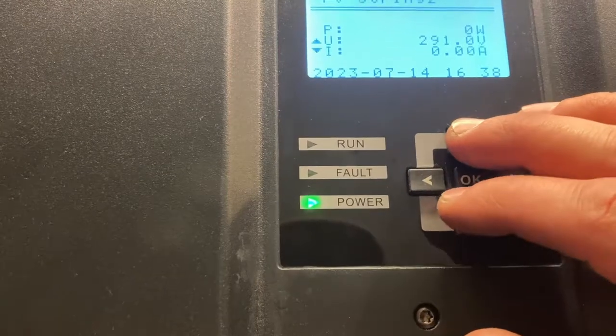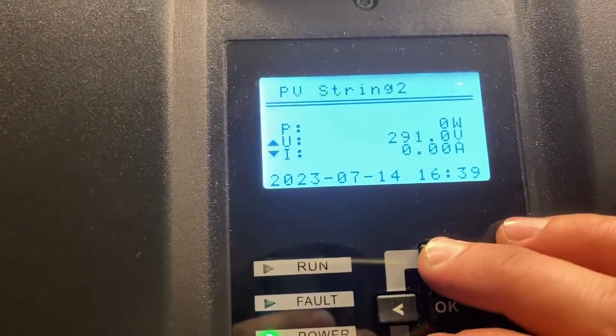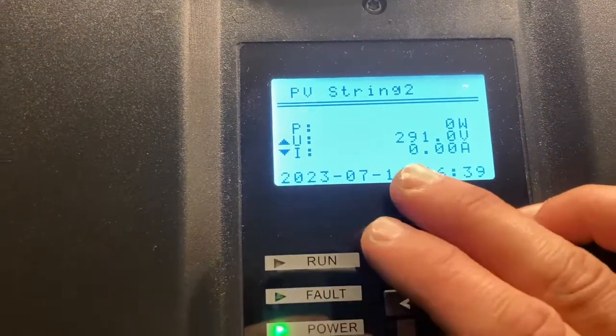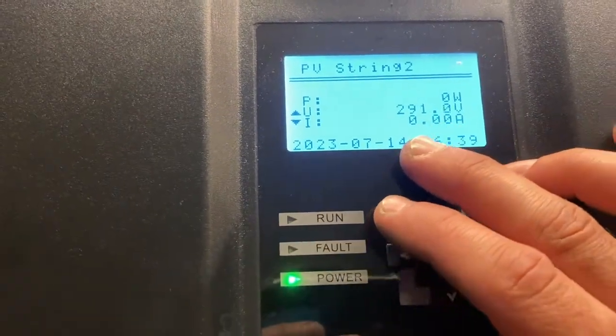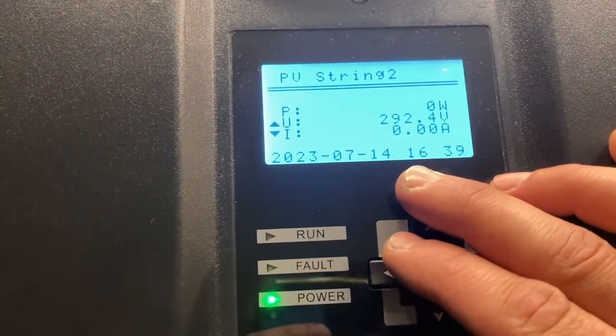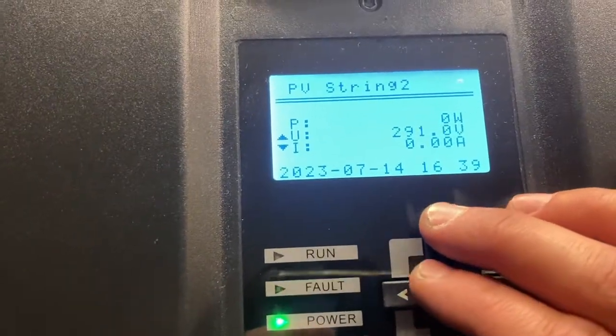All right, so string 2, PV String 2 - oh, hold on, we're getting it on string 2, so I must have it on string 2. 292, that's a bit high, but it's within the range for the machine, but we're not doing any current.